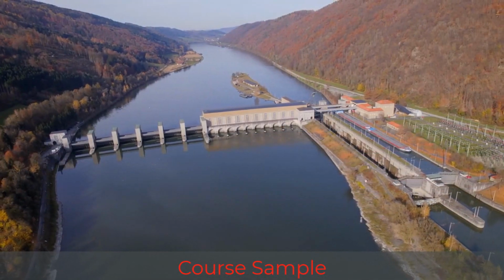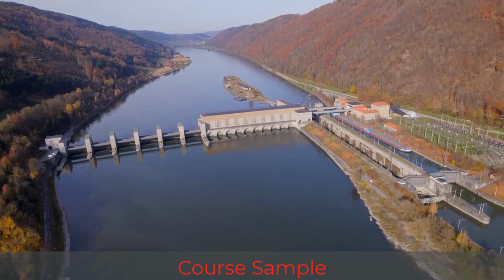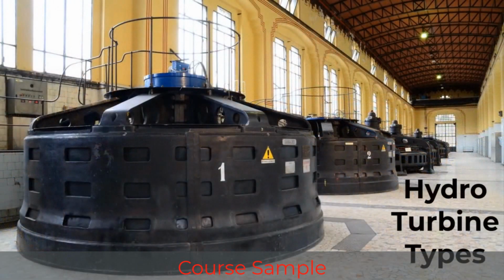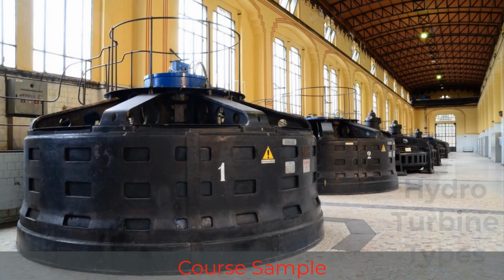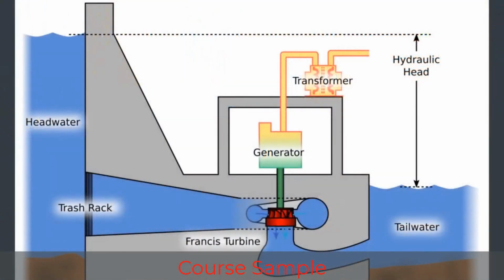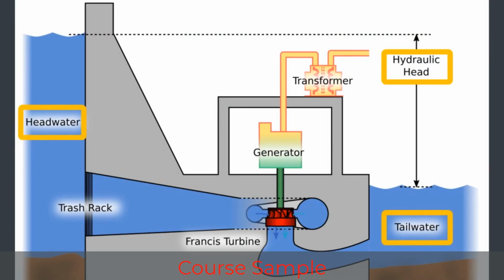Let's have a look at the 3 main types of turbine that you're likely to see within these power plants. The type of turbine employed within a hydroelectric power plant depends upon the availability of flow and the head of pressure. The head of pressure is the difference in elevation between the headwater of the power plant, which is the body of water upstream of the power plant, and the tailwater of the power plant, which is the body of water downstream of the power plant.